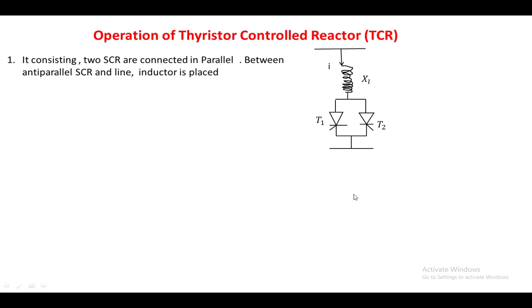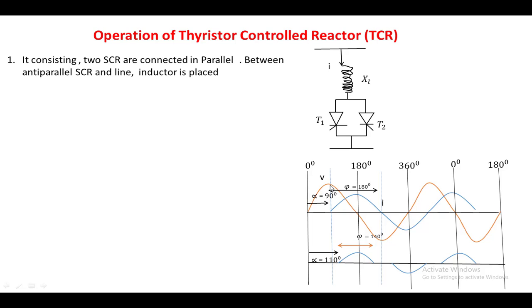For the operation of the thyristor controlled reactor: T1 and T2 are connected anti-parallel in series with a reactance, and voltage is applied across the system. Looking at the voltage waveform, during the positive half cycle T1 is forward biased. A triggering pulse is applied to T1 at a firing angle of 90 degrees, so T1 begins conducting from that point.